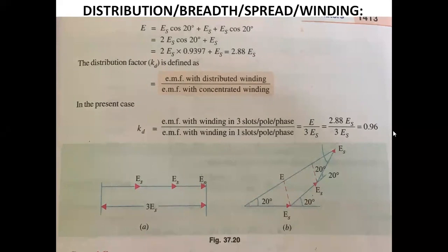Now these 3 coils constitute one polar group. These 3 coils are not bunched into one slot. They are not tied together and kept in one slot, but are distributed. This forms a polar group. So this distribution of the bunch is called the distribution factor.